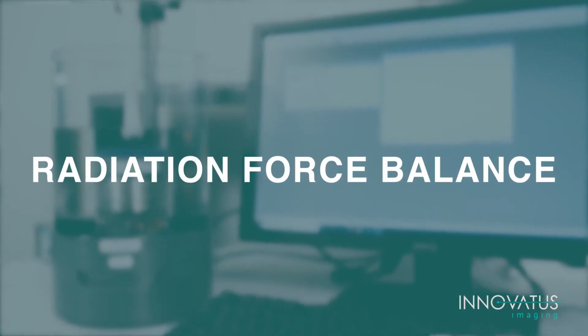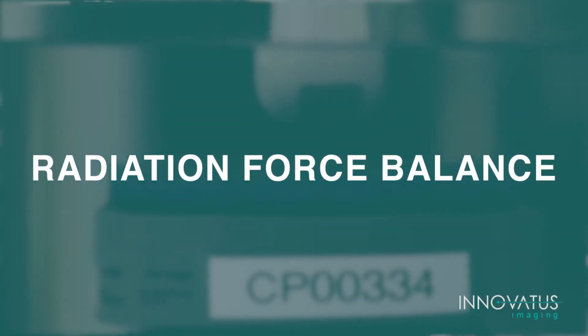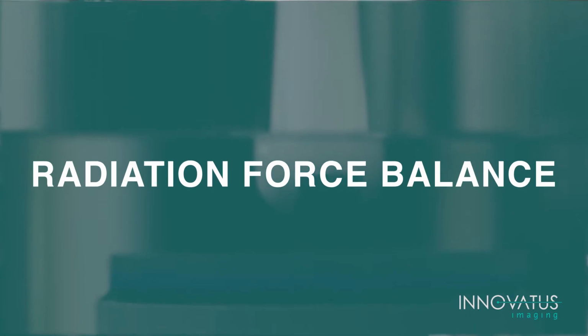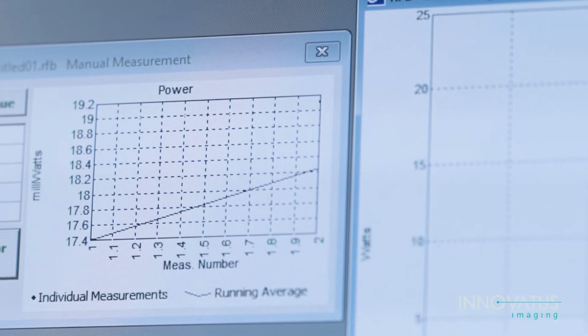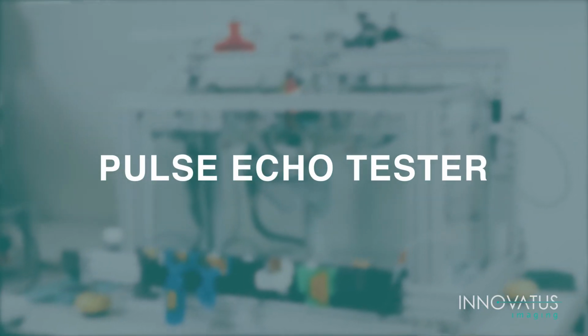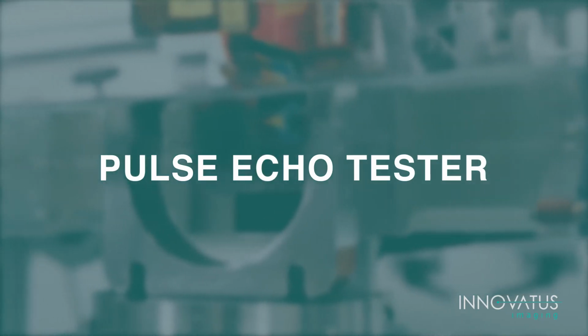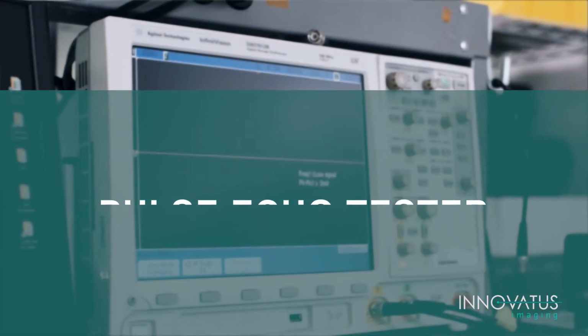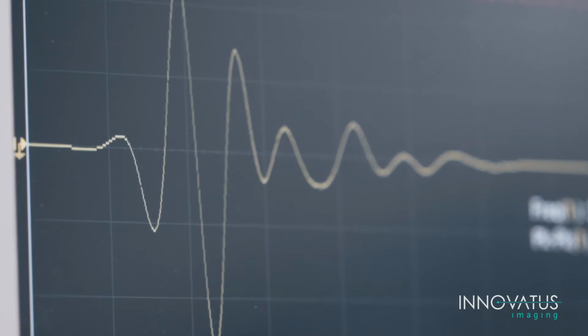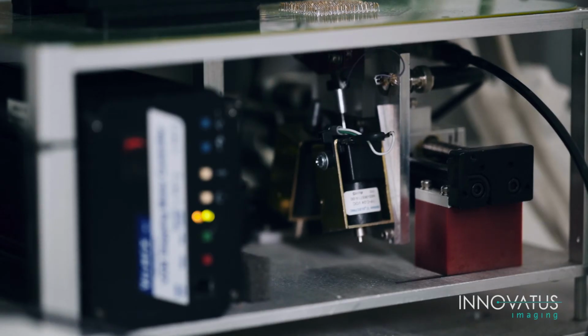The other piece of equipment associated with acoustic power is a radiation force balance. This is a little bit of a simpler piece of equipment, but it's critical to the characterization of safety parameters for a new or repaired device. A pulse echo tester is a critical piece of equipment for any array manufacturer. This allows us to apply a transmit pulse and record receive characteristics on every element of every array that we manufacture, ensuring that we have a consistent product and a product that performs as we expect it to.